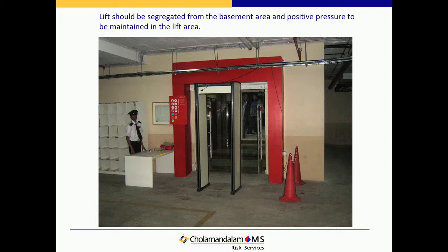Lift is coming up till the basement. Lift should be segregated from the basement area, and positive pressure to be maintained in the lift area. So in case of fire, the lift should not be working, and even if it comes, it should not come to the basement, because the basement is where you park all your vehicles, and fire from that can spread to the other areas.